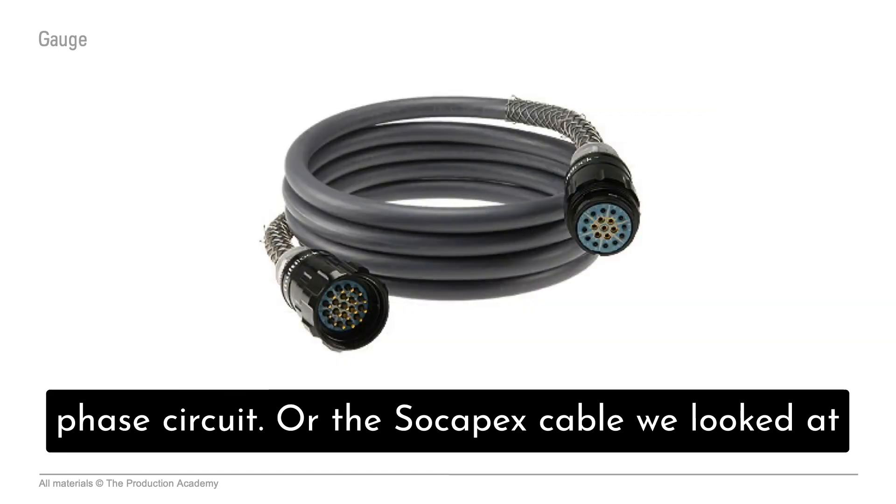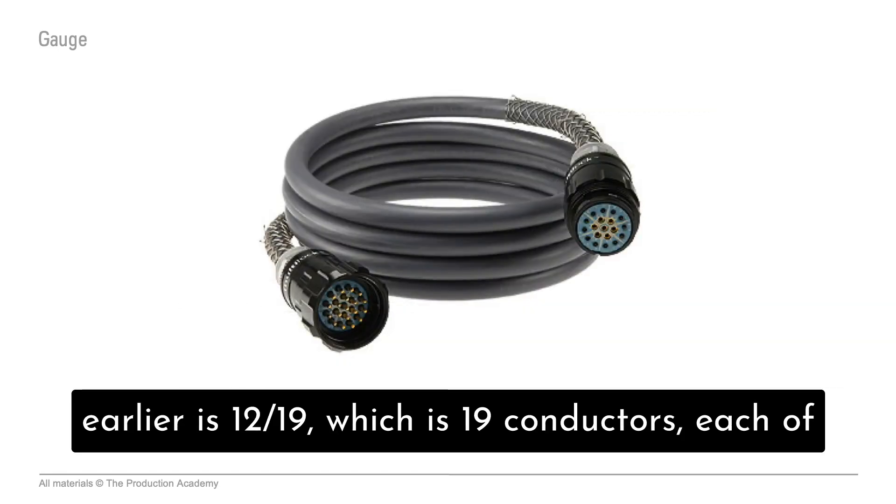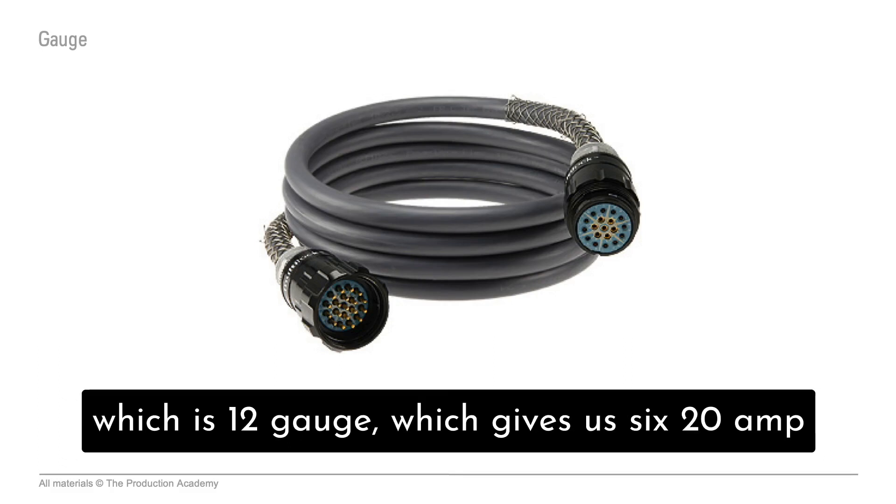Which we can use for one 20 amp single phase circuit. Or the Socapex cable we looked at earlier is 12/19, which is 19 conductors, each of which is 12 gauge, which gives us six 20 amp circuits.